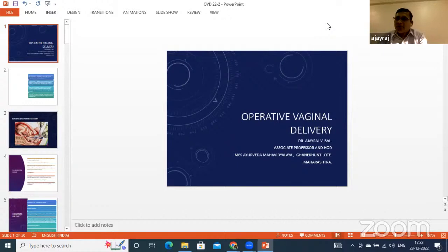There are two knobs. On the vacuum machine, you can adjust the pressure from 15 to 20. That is sufficient. In some cases, you may require up to 25 also. It is calibrated from 0 to 30. So the pressure should be around 15 to 20. If you see that the pressure is going to increase, or the machine is not calibrated, there is a kind of knob or screw placed at the zero side of that manometer, and we can adjust the pressure with that knob. If you see the machine, you will see that.